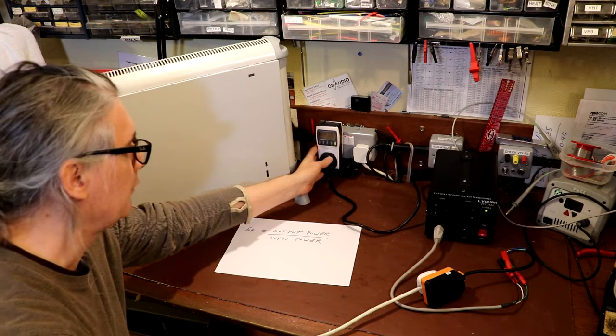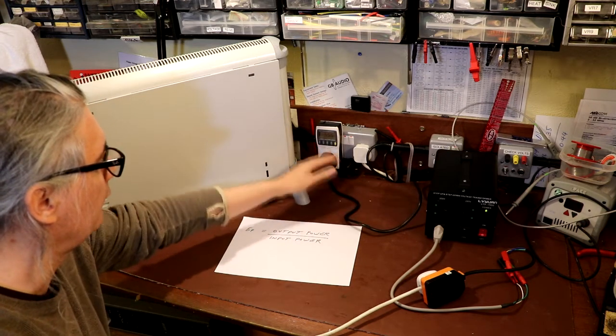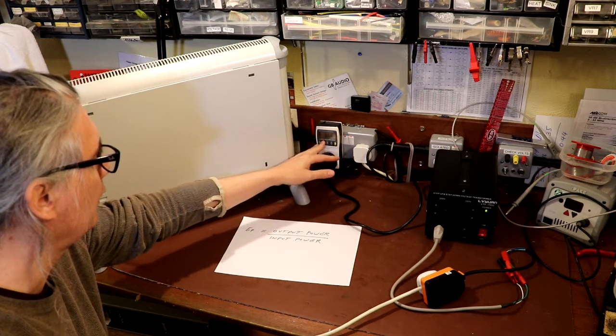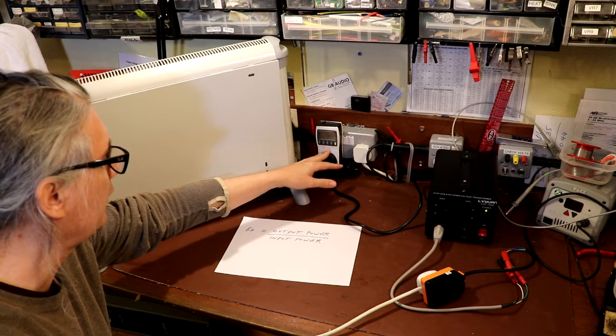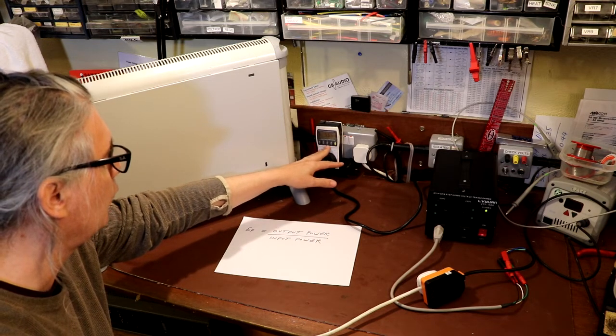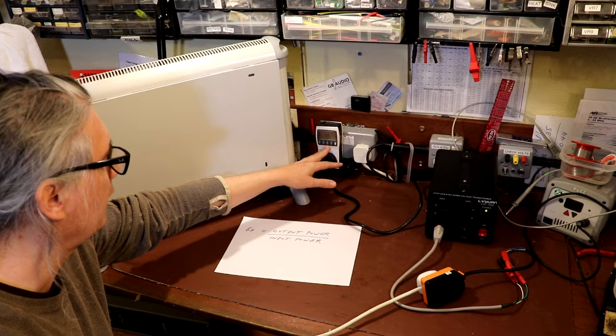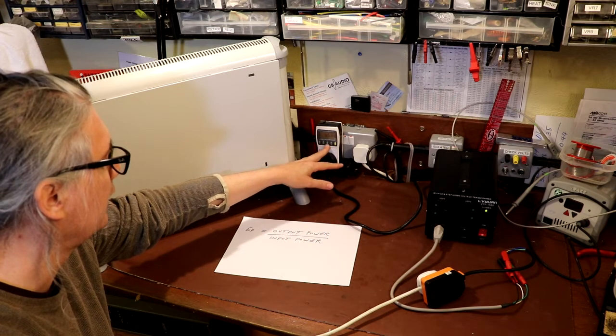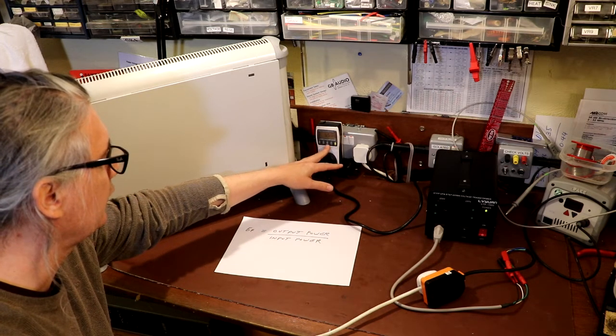We're supplying our transformer here with power from the socket through this energy monitoring plug, which I've set to show watts. A lot of these plugs have a watt setting and a VA setting, and it's important for this test that it's set to watts.